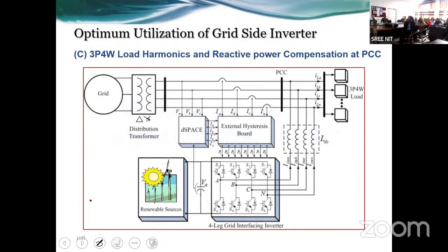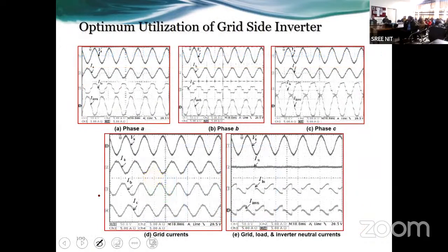So this was the 3-phase 4-wire system. Again, I just modified it a little bit, because fourth means unbalanced current is also there. So what we did is that the unbalanced current, neutral current, is also shared by this neutral wire from here. So the grid is always having a perfect 3-phase system, perfect balanced load. I will show you in the next slides. See, this is phase A, phase B, phase C. All the loads, phase A, phase B, and phase C, they are different.